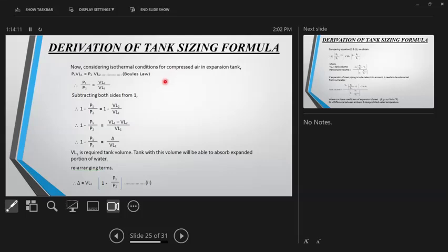So with reasonable accuracy, you can always say that the air or nitrogen in the system has not undergone much change in temperature. So for such a system, you can always apply Boyle's law. And what Boyle's law says is PV equals P1 V1 equals P2 V2. So I can apply P1 VL1, the earlier volume and the earlier pressure, and increased pressure and reduced volume. So this is Boyle's law, which with very little error I can apply to the system.